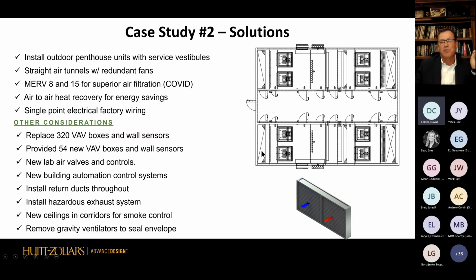Now we can start controlling the air in different areas of the building. What we've done is, there are dampers here, and we can return the air exhausted out here, and bring in air. These are heat pipes - the technology's been around for 100 years, and we can recapture 60 to 70 percent of energy. Now the building, these are becoming big fresh air machines, really - so real simple, passive technology.